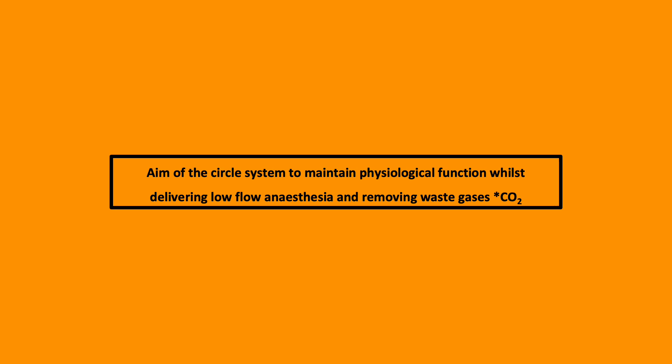It is classed as a closed system when the APL valve is fully closed and semi-closed when the APL valve is partially open. The aim of the Circle System is to maintain physiological function whilst delivering low-flow anaesthesia and removing waste gases.